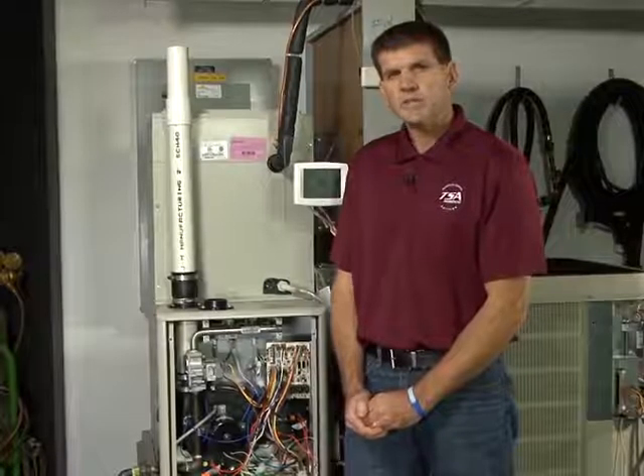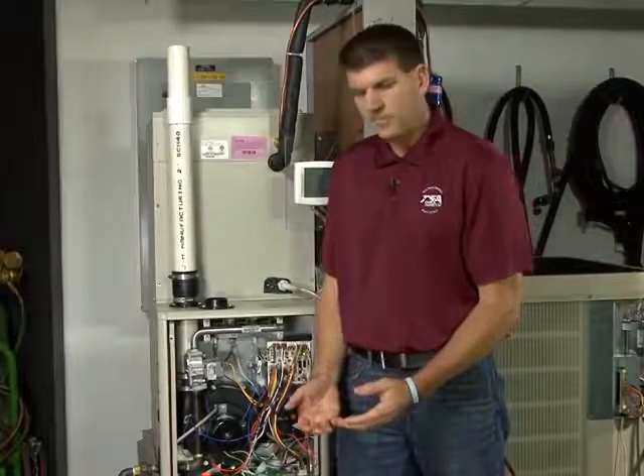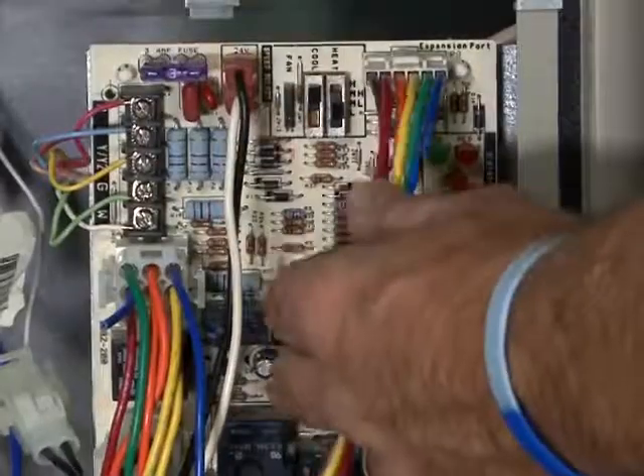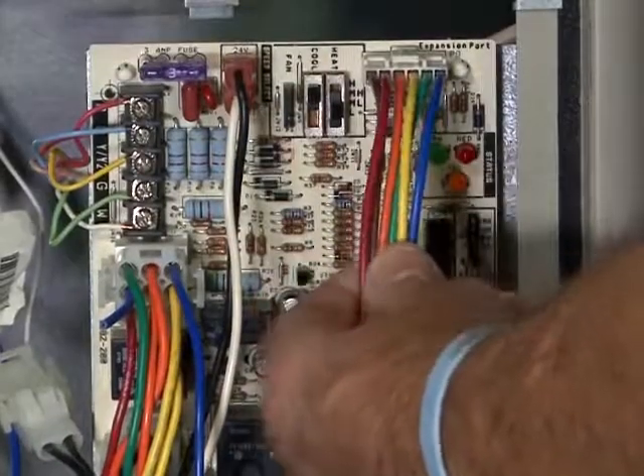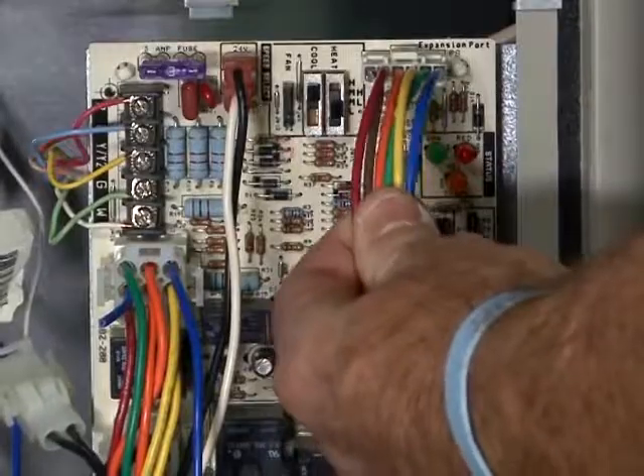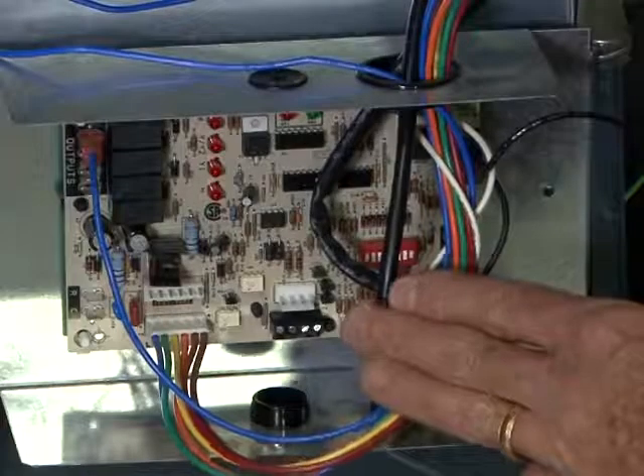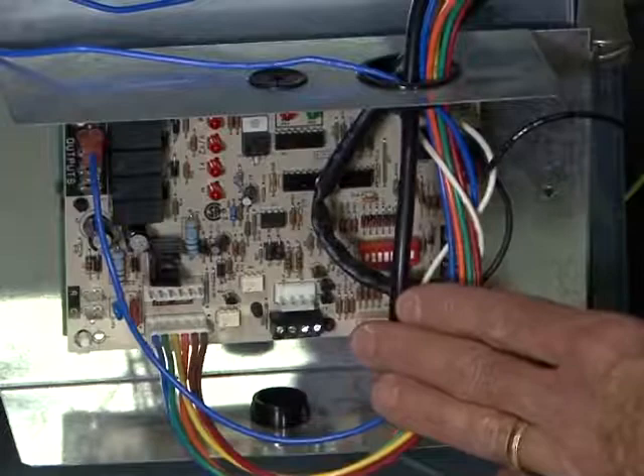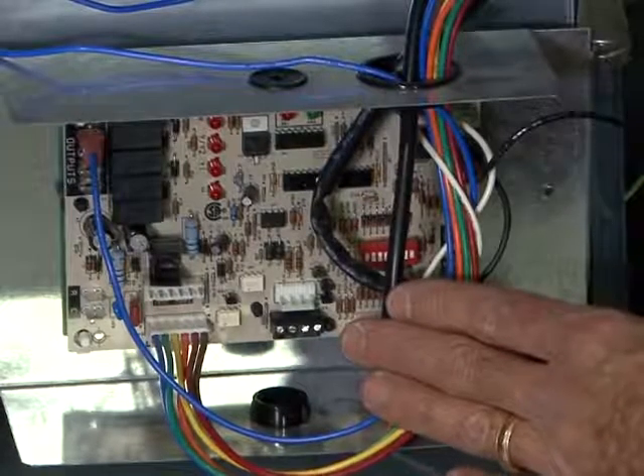One of the fault codes is a communications fault, which is indicated on the motor board, and the motor fault, which is indicated on the motor board and the interface control board. If you're getting a communications fault, this generally indicates the motor board is bad. The one thing to check for is connections between the motor board and the main control board. These two boards are connected at the expansion port connection on the interface control board and down at the motor control board. You will want to make sure that your connection is good and tight in both places.